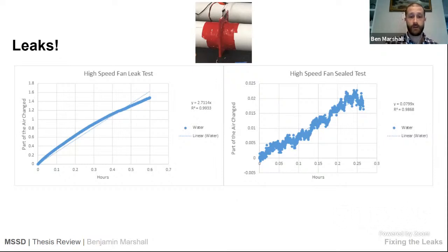The little equation on the top right of each graph shows y equals something times x. That something is the air change rate. So I was changing out 2.7 times my air per hour, which is way too high, because the amount of water I was going to capture in the stream was very, very low. So I needed the leak to be very low, or else I wasn't going to be able to see it.